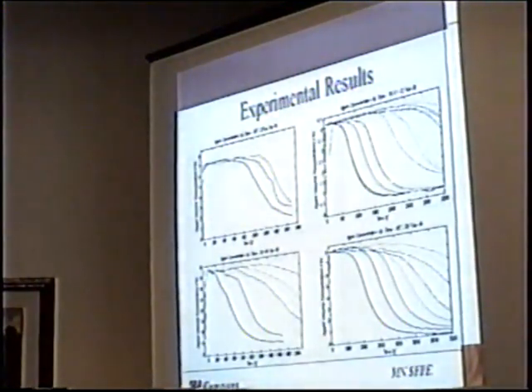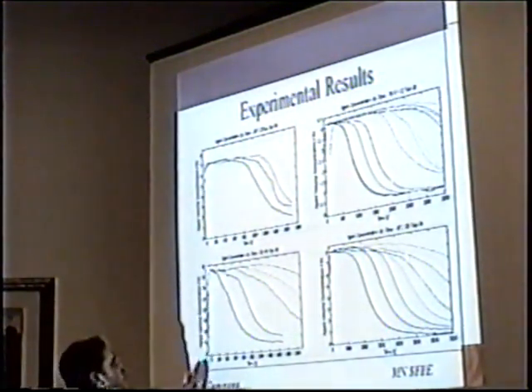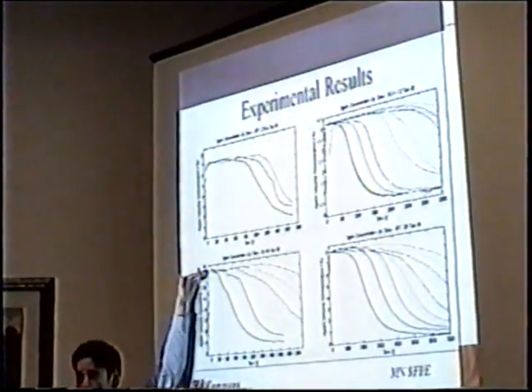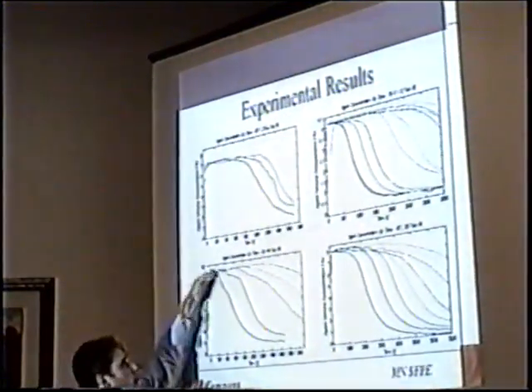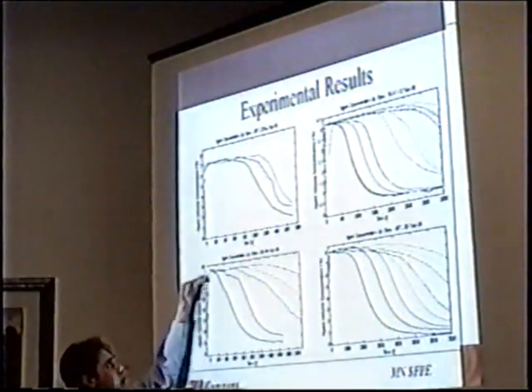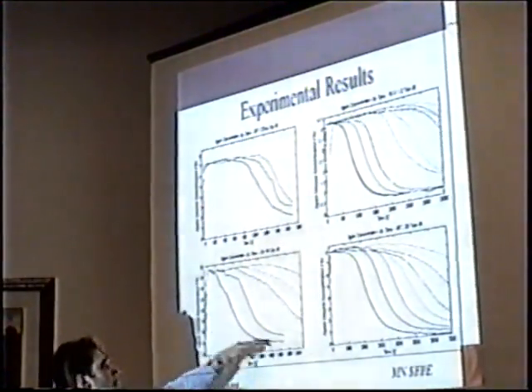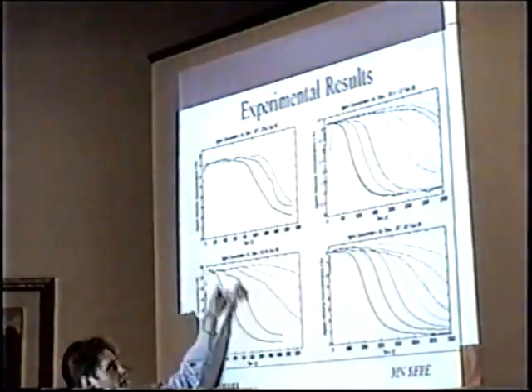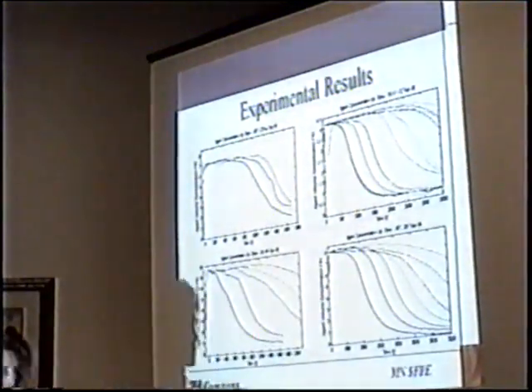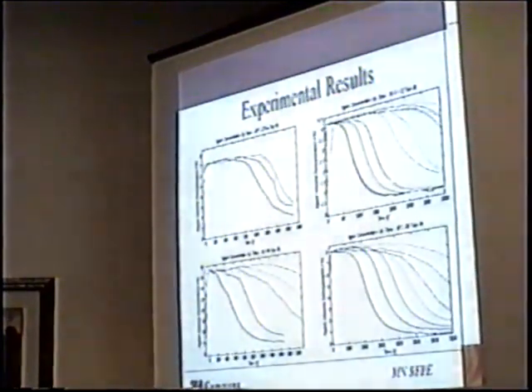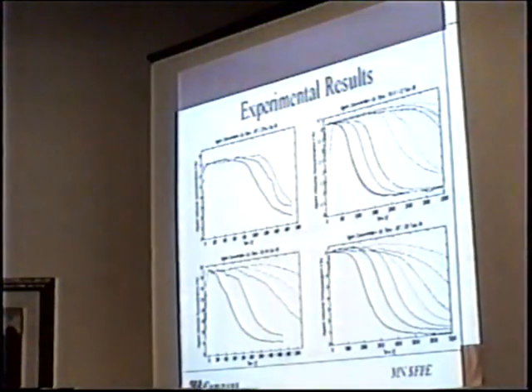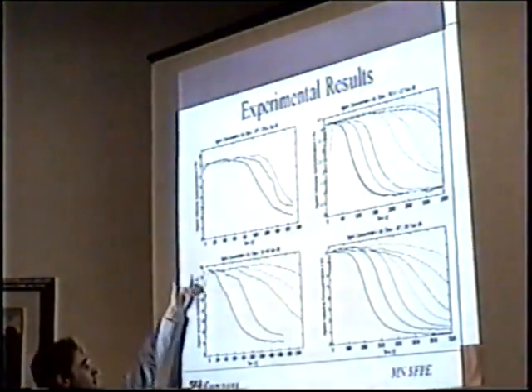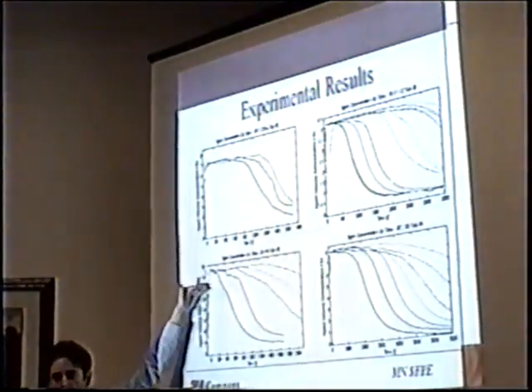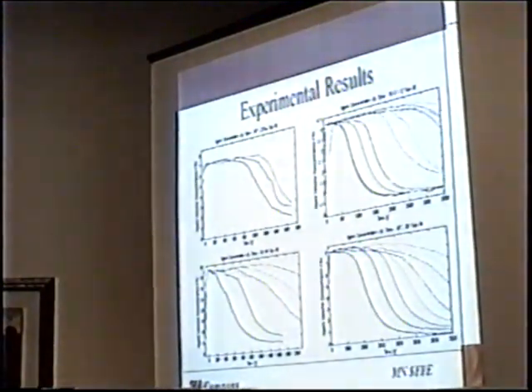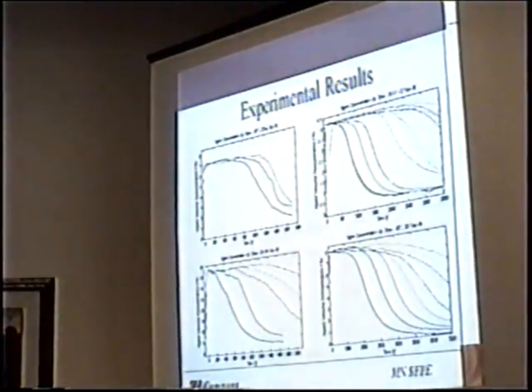So this is looking at the raw concentration data here. The general trend that you see is that discharge occurs. There's a spike in concentration of whatever particular agent we're dealing with. With time, as the interface begins to fall, one probe will see the interface pass. As time progresses, another probe sees it, and another, and another, and another. So essentially, we filter through this to pull out what our failure points are. The typical criterion is to say, look at about 75% or 80% of the initial concentration, somewhere right in there. Then we just draw a line and see where these lines cross.